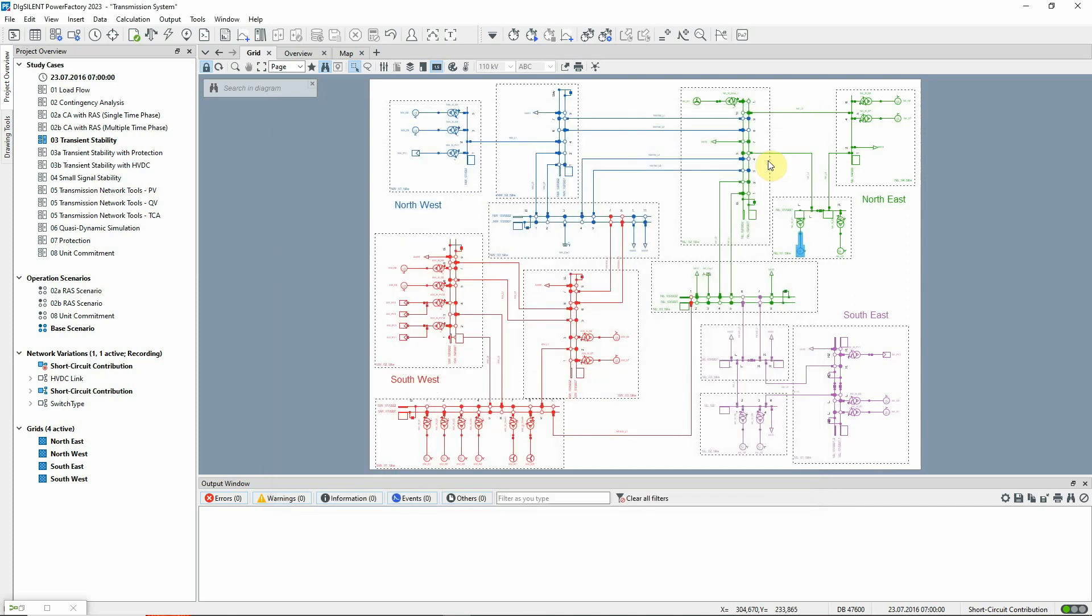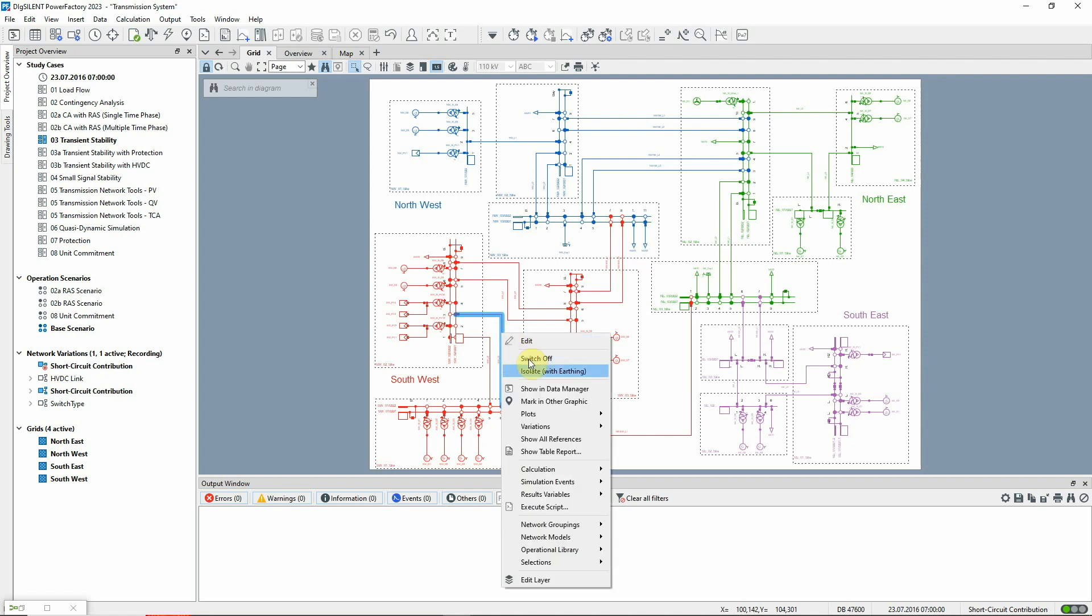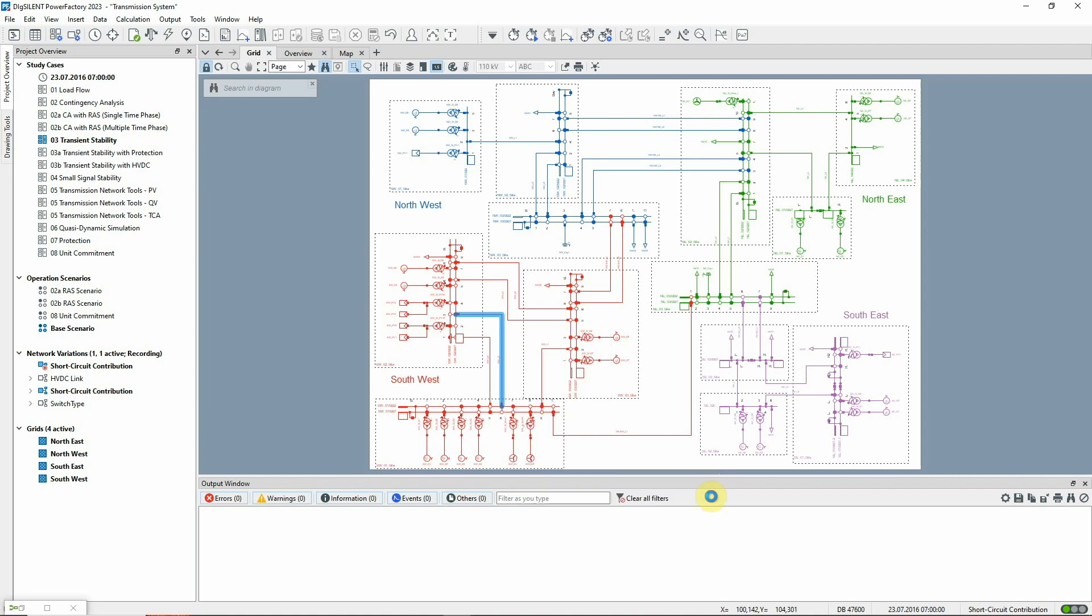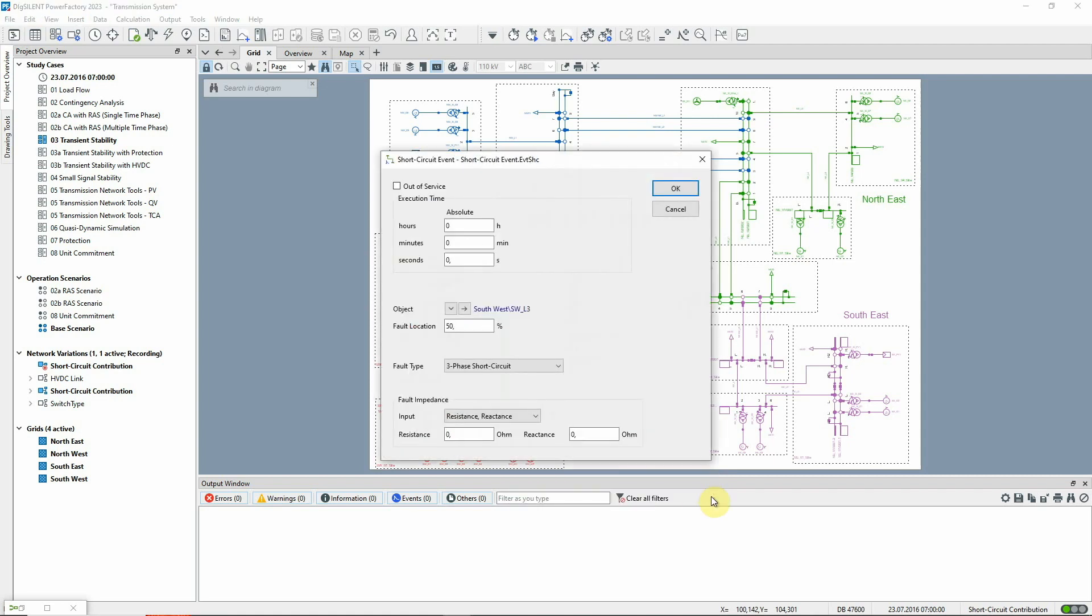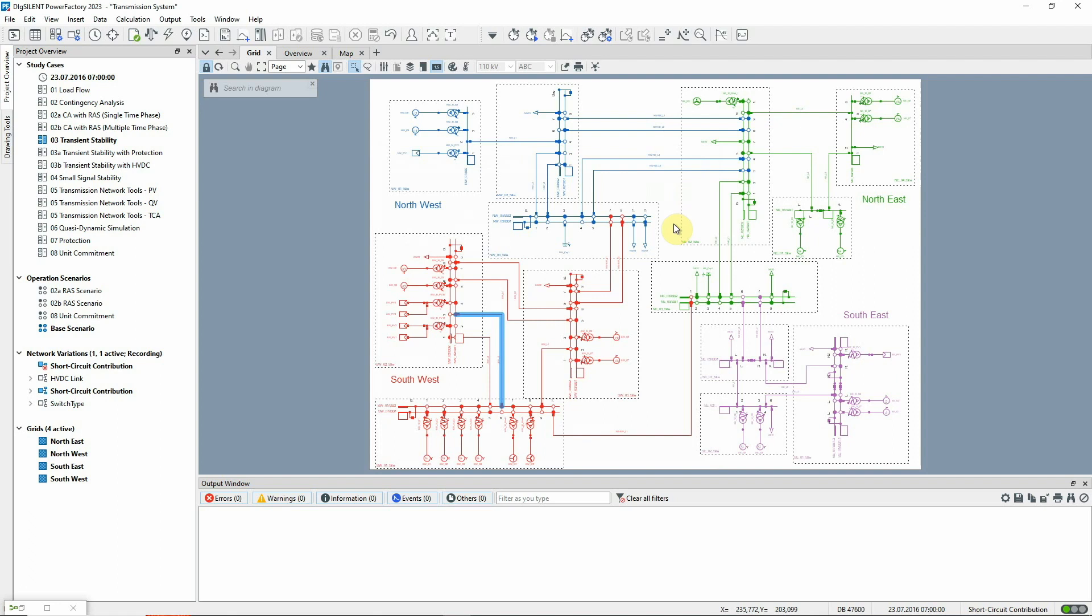To carry out a simulation, we first need to set up the events to be analyzed. We'll study a fault on the line SWL3. By right-clicking on the circuit from the grid graphic, we can define the short circuit event. By default, this is a three-phase fault halfway along the line, which occurs at zero seconds. We also need to clear the fault after a suitable interval.